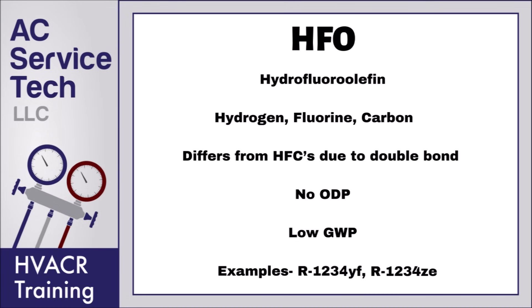HFO refrigerants were developed to reduce greenhouse gases and they differ from HFCs due to the double bond, which helps them break down in the atmosphere faster. HFO stands for hydrofluoro olefin, made up of hydrogen, fluorine, and carbon. These refrigerants have no ozone depletion potential and a low global warming potential. Examples are R1234yf, used in the automotive industry as a retrofit for R134a, and R1234ze, primarily used in chillers and commercial refrigeration.